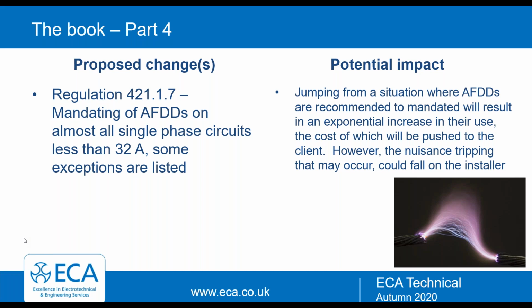The biggest reason for that is that AFDDs in themselves can't detect arcs less than, I believe it's 2.5 amps. So there's a limitation on that. It's effectively pointless putting it on a domestic lighting circuit because of that. Yeah, it's got to have a certain load on to be able for the AFDD to actually function and be able to see it. So it's anything less than a 6 amp breaker is possibly not going to have enough load to make it work, and anything more than a 32 amp breaker, they don't make them. Okay, so it's a small amount. And single phase as well. There's no 3-phase version either. Okay, so it is a little bit more restricted.